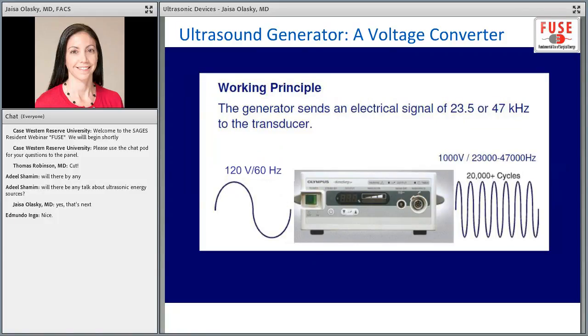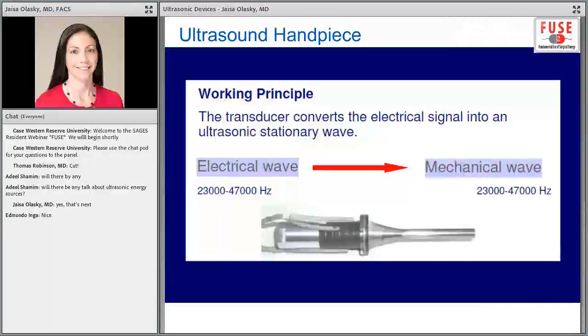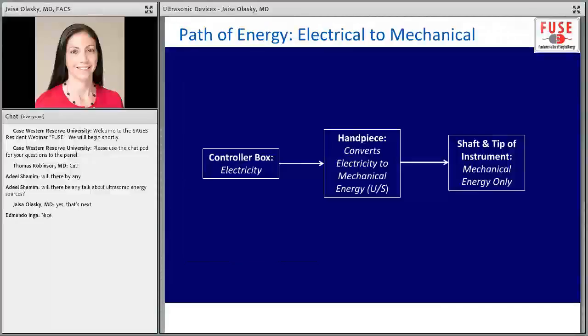Before it gets to the handle, the energy goes through a generator. For most machines, it is plugged into the wall and goes through the generator before it goes to your device. There are also some devices now that have lithium batteries that power them instead. As I mentioned, once it gets to the handpiece, that's where the electric wave goes from electricity to mechanical energy, and then ultimately into the device where it's mechanical energy only.